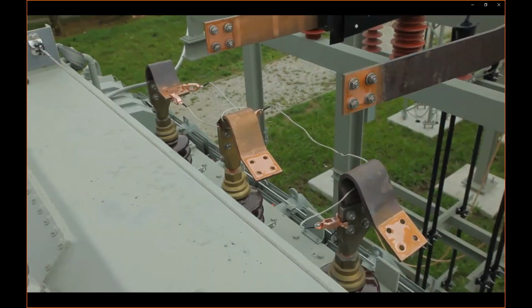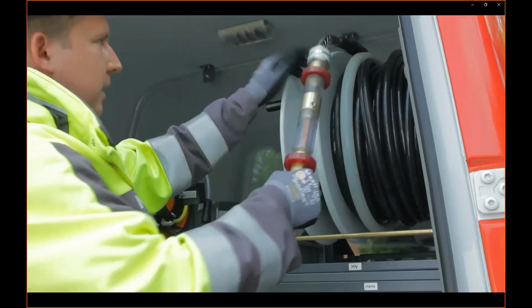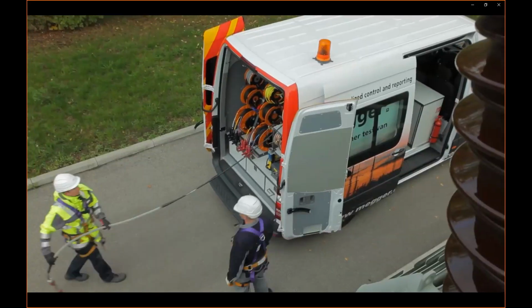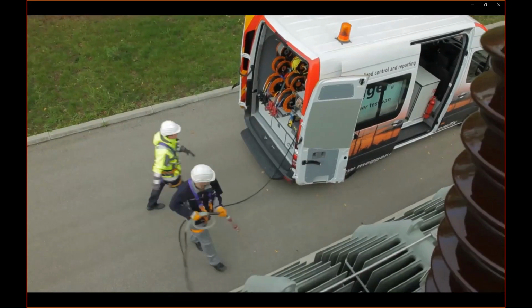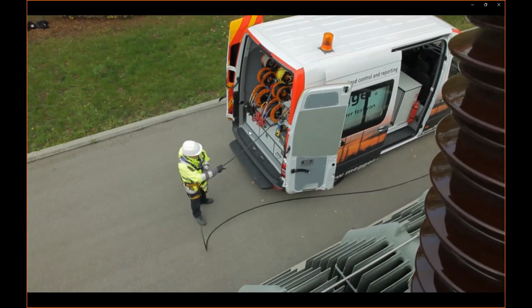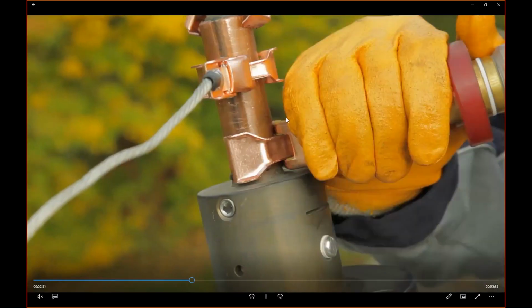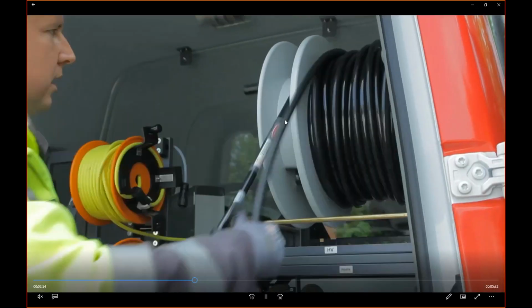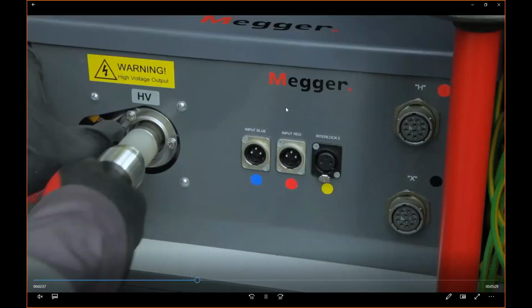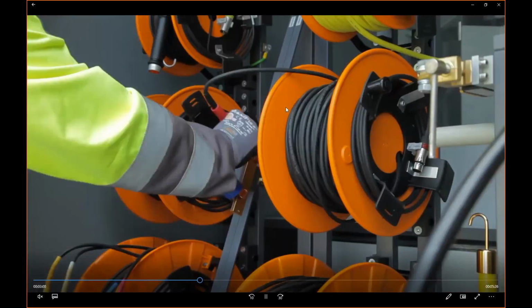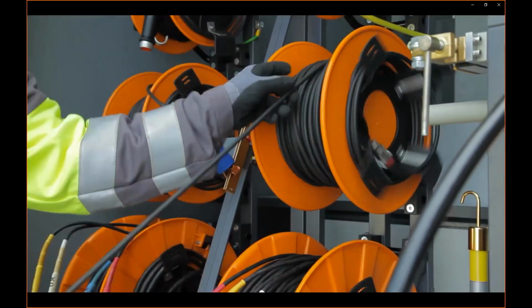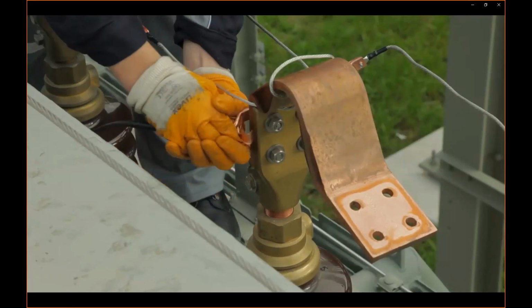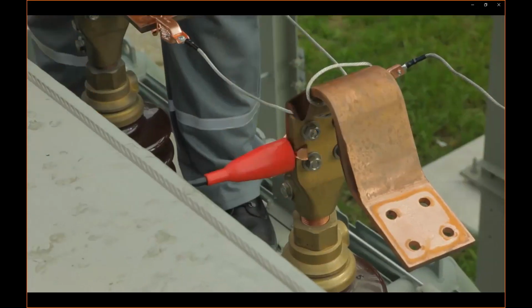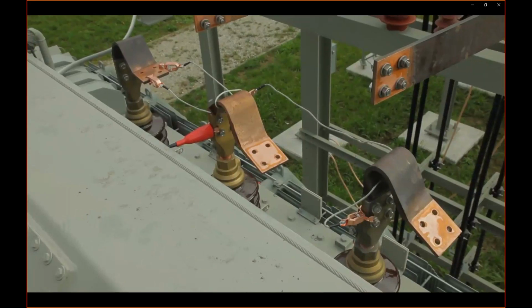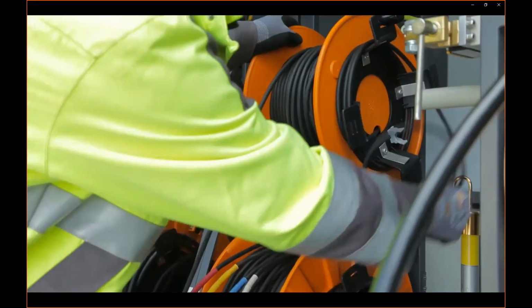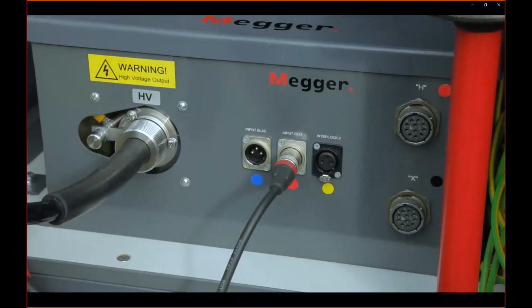And of course, we will now be connecting the test van. So the HV lead is taken out and brought to the top and connected to the HV side. And the other end of the cable will be connected directly to the switch box. This is what you see. Now, depending on how complex your transformer is, for a 2-winding transformer, you just need to connect a red lead on the LV side, and you are good to go. So you close the doors, and you go and operate the software.